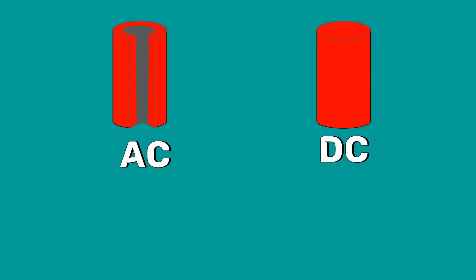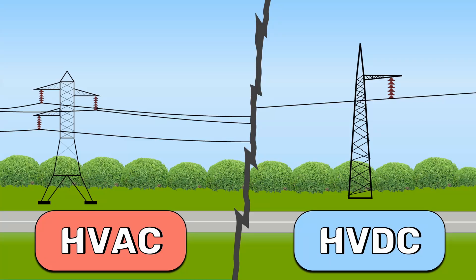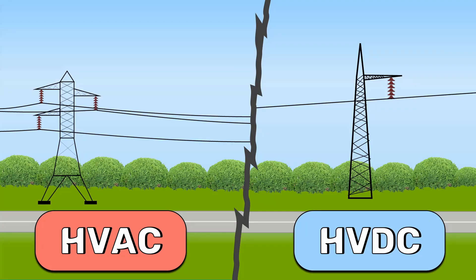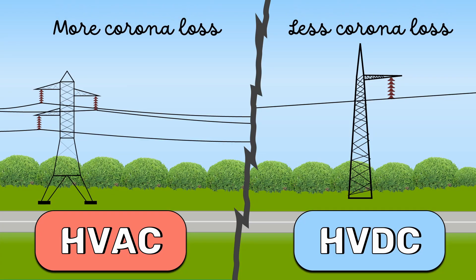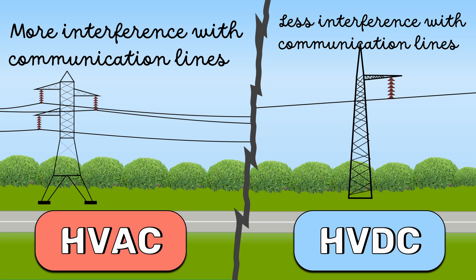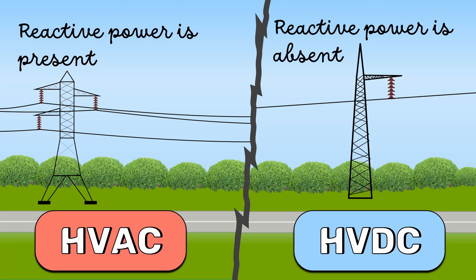Comparing the two systems: for the same amount of current to transmit, AC transmission requires a conductor with a larger diameter. This means HVDC transmission requires thinner conductors than HVAC transmission. Corona loss will be less in HVDC transmission than in HVAC transmission. Interference with nearby communication lines is less in the case of an HVDC overhead line than an HVAC line. The absence of reactive power in HVDC transmission also reduces the power loss in HVDC.